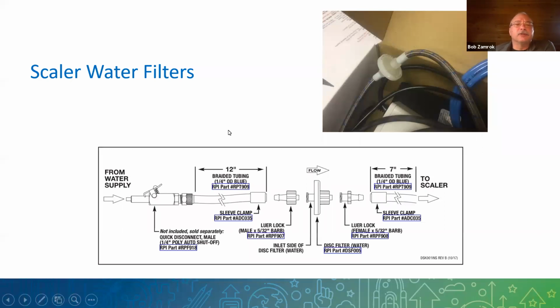Scalers, Cavitrons - this is another item where we get no water out of a Cavitron. There's an illustration on the bottom of the screen that shows from your water supply all the way to your scaler. There's a little disc that's the water filter, and that needs to be replaced. It really depends on where you're at and what kind of water you have, how often you need to replace it. It's a translucent device, and you'll see it gets darker as it fills up with sediment. You just replace it as needed.